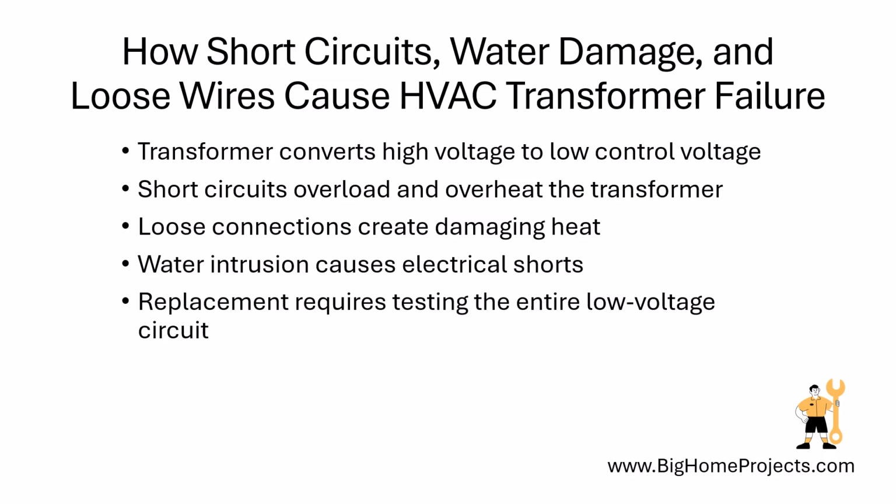conditioner, or heat pump. The most common cause of failure is a short circuit in a control wire, relay, contactor, thermostat, or another part connected to the transformer. When that happens, the transformer may try to send too much electricity, causing its small internal winding to overheat.